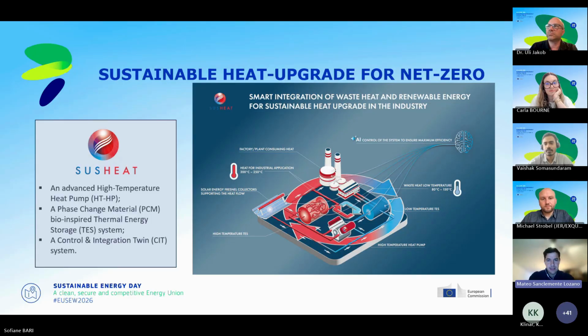So the concept that SUSHEAT proposes is that we can take the waste heat that is currently not used or curtailed in the factories. We can recover this waste heat and upgrade it through the high temperature heat pump, which in our case is a Stirling heat pump using helium as a refrigerant. We don't have any phase change within the heat pump, because it's only compression and expansion of the helium. So we can recover heat from the waste heat through the helium, upgrade it to a higher temperature level, around 200 to 250, and deliver it to the process at the temperature that is required, right?